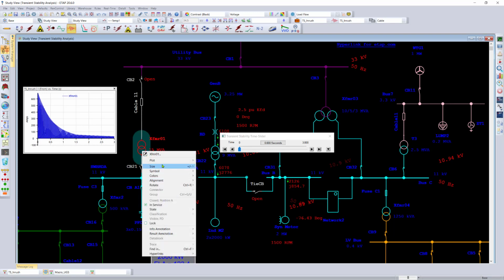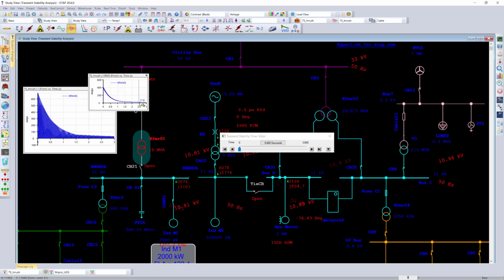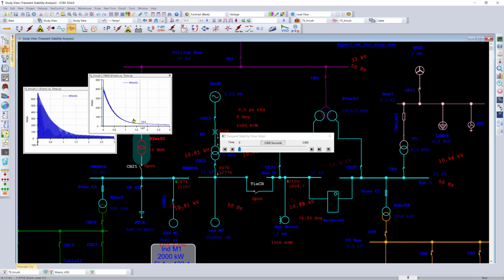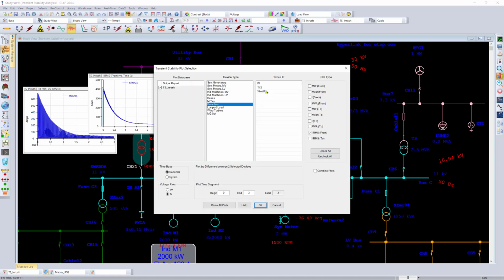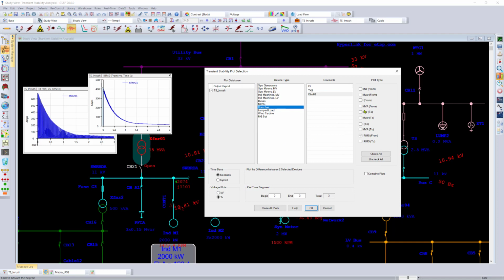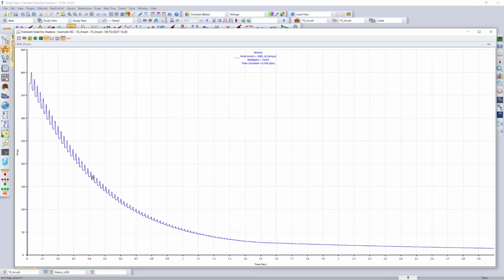So therefore, one of the things that we've added in ETAP 20.6 is essentially an RMS envelope for the inrush current. So this helps us visualize a little bit more clearly how the inrush is actually decaying in the system and what the peak value is. You can go inside the plot view and pick the transformer that we are using in our simulation, select the inrush curve in RMS, which is new in ETAP 20.6, and click OK. And now you can see the actual envelope of the inrush, but you can also see the inrush value, the multiplier, as well as the time constant.